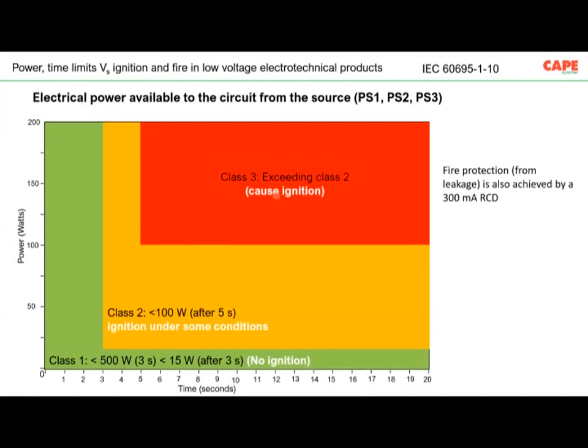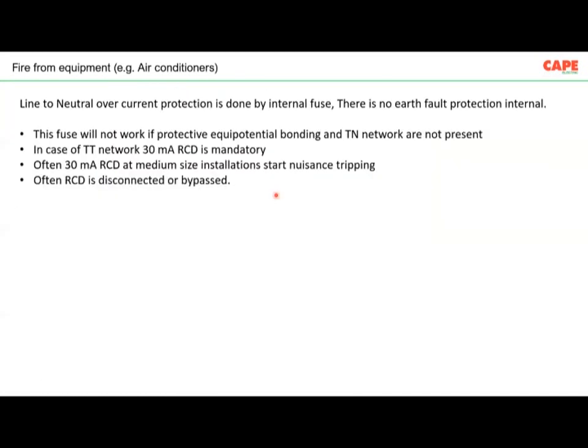You have an air conditioner. The air conditioner has an internal fuse. Whenever there is a short circuit or an overcurrent between line and neutral, your fuse will blow and the device is disconnected from the circuit. But the same fuse will not disconnect whenever there is an earth fault. If you want your air conditioner to disconnect, then your earth fault loop impedance must be negligible. Only then will it work out.